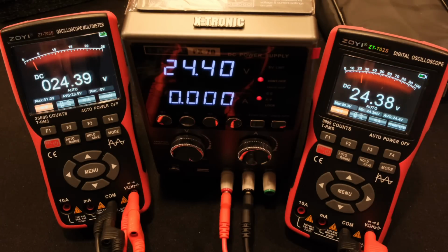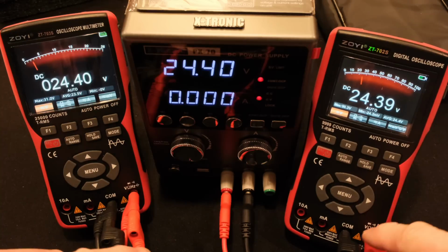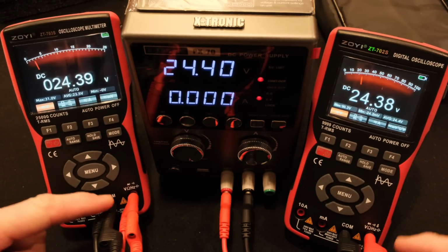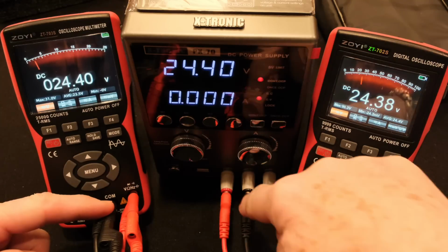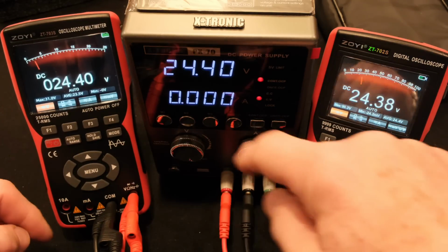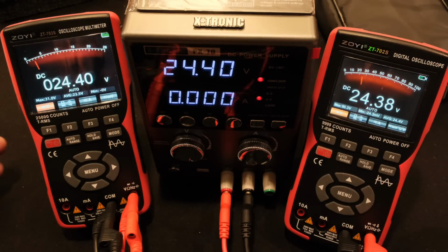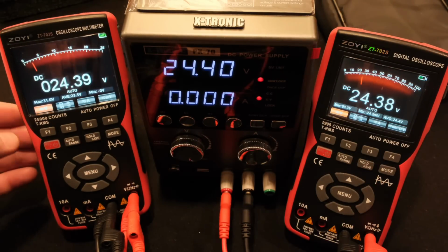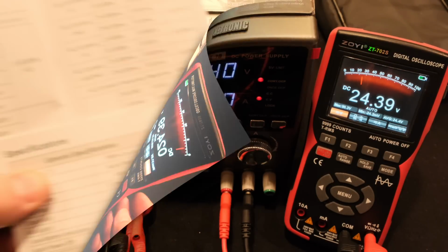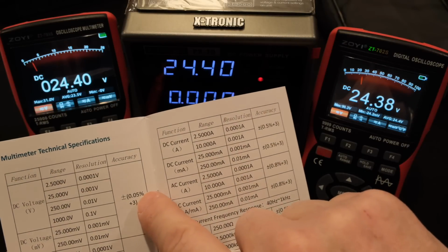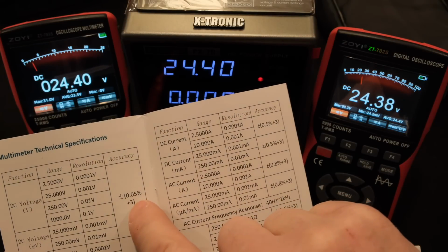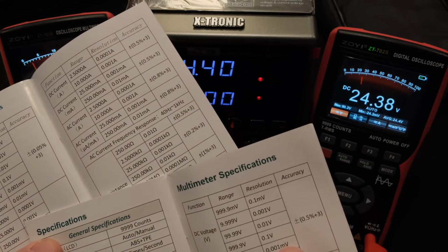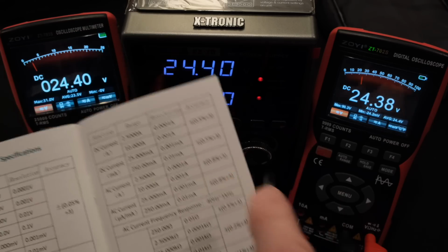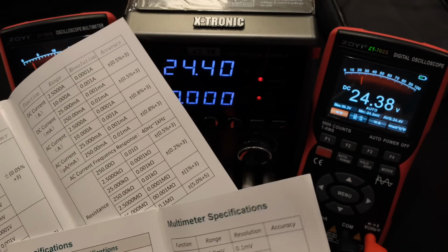All right, so what we have here is this set of leads connected to this meter, so the two meters are connected together, and then this one going to the connection here. So both meters are reading essentially the same voltage, right? Well, first of all, let's cover the tolerance. This book is for the new one. It's 0.05%, which is pretty darn good, plus 3 digits on the last digit. So 3 counts.